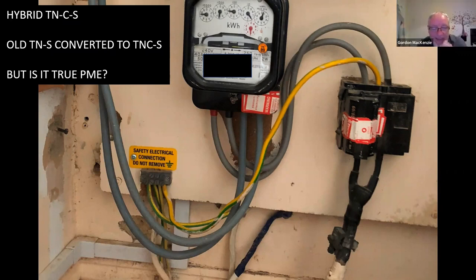An exposed earth connection there as well. It's not even as if it's enclosed. Your neutral earth connection now is exposed, and the sheath of the cable terminal is exposed as well. So you get two different. Just also to be clear, there is a GRP cutout surrounding all that now. That's what it was when I moved in. So yes, but I still have control of it. But yeah, I get what you're saying.